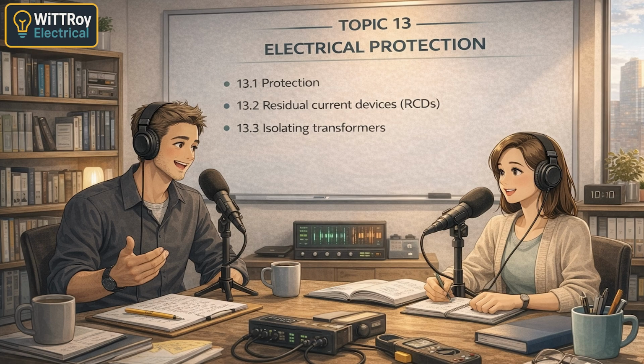Yep, and an important exam point, rewirable fuses are not permitted in new installations. That's under AS/NZS 3000. Correct. They may still exist in older installations, but not for new work. So if the exam asks, rewirable fuse equals coarse protection. Exactly. Now let's look at common excess current devices.